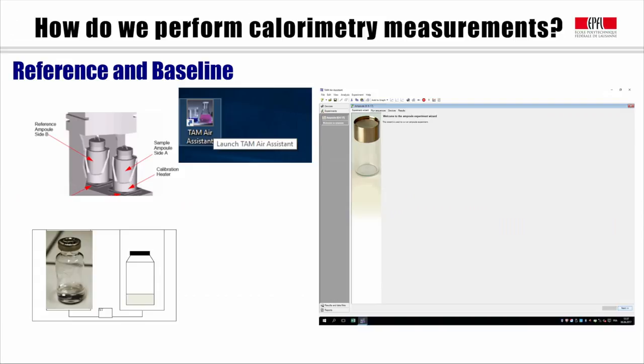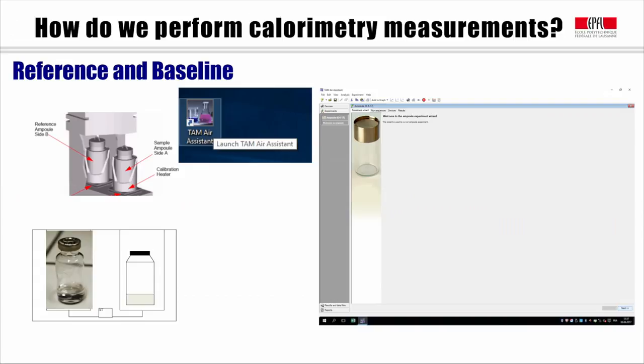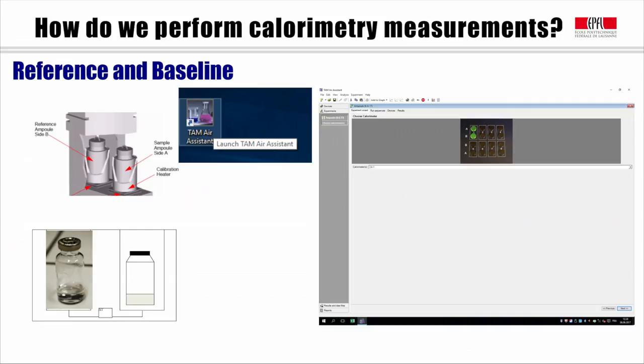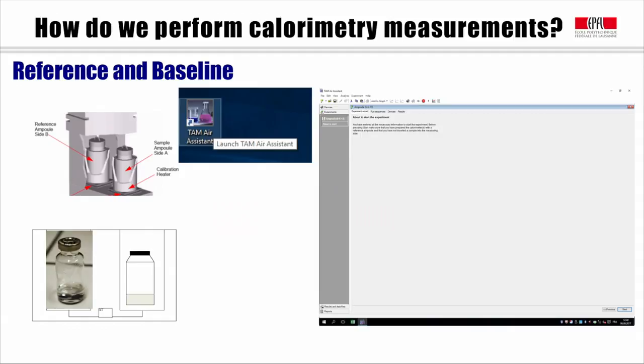In next window, you will be reminded to put the reference water inside. And also, you need to put the baseline duration and signal stability condition. Different conditions tell the end of the baseline when different conditions are met. Usually at 20 degrees, the baseline with this condition takes around 30 minutes. If the temperature difference between the reference water and the instrument is higher, then this time, of course, will be longer.